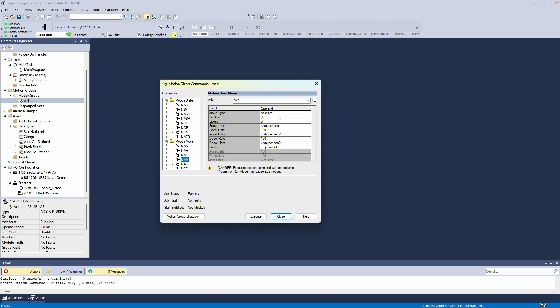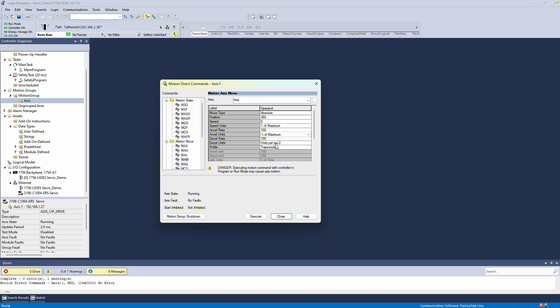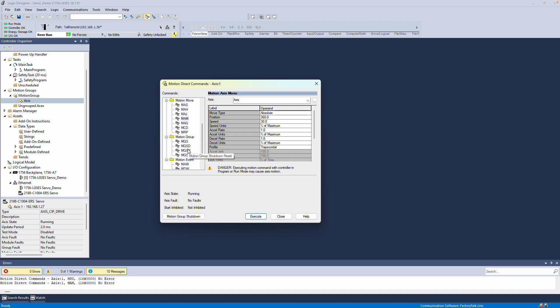The next command we'll look at is Motion Axis Move. This command offers several options. For this demo, we'll choose an absolute move and set the position to 360 degrees for a full revolution. I prefer setting the speeds as a percentage of the maximum, so I'll set everything in percentage terms and adjust the acceleration and deceleration rates to around 1% with the speed at 30%. Press Execute and the servo will move accordingly. This is how you get your servo drive moving.